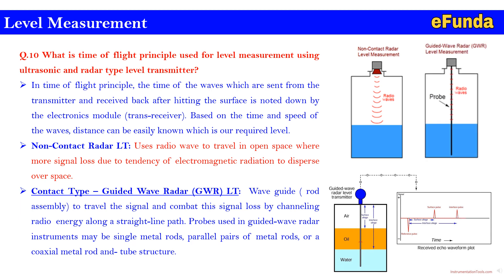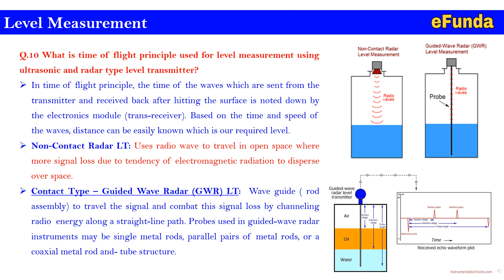The second type is contact type guided wave radar (GWR), which uses a rod assembly as a wave guide to channel radio energy along a straight line path, combating signal loss. GWR instruments may be a single metal rod, parallel pairs of metal rods, or a coaxial metal rod and tube structure.